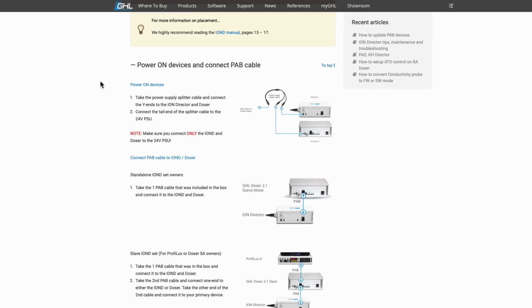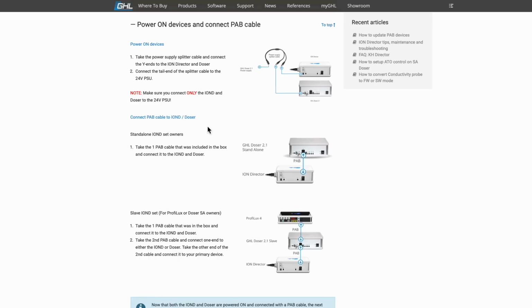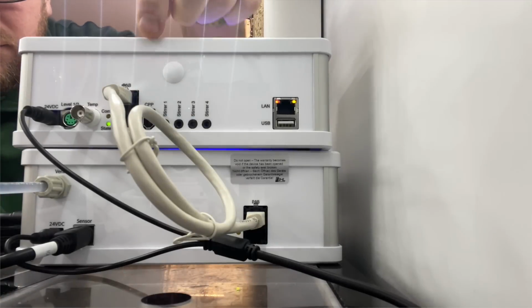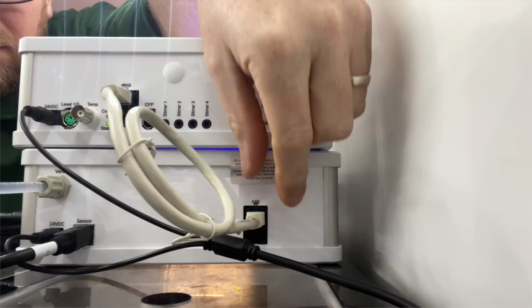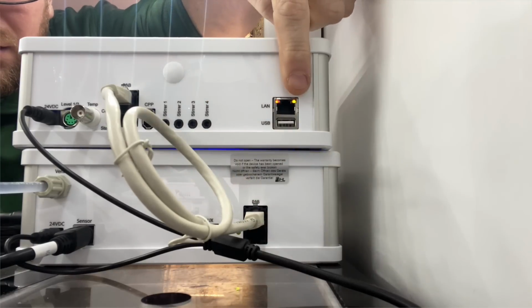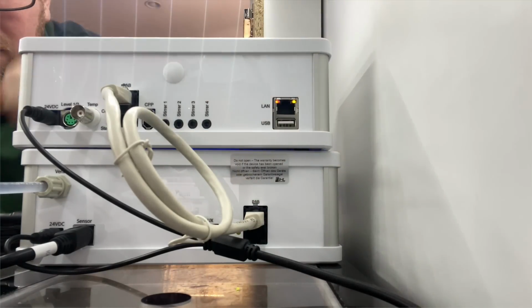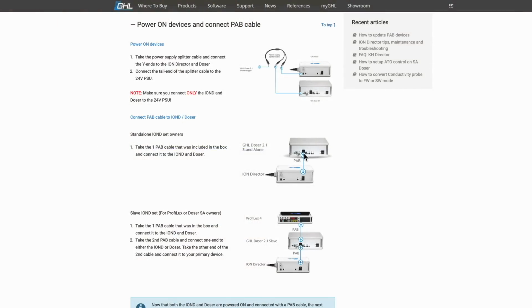The first real step you have to do after just setting it down somewhere is to power it on, which, I don't know, I found interesting. So you find a location, plug the power into both units and turn it on. Easy enough. And you can then connect the PAB cable, which seems odd. I thought you would connect the PAB cable first, but you power it on, then connect the PAB cable, which, like I touched on, is basically that Ethernet cable, but it is labeled PAB on the doser. Don't connect it to the LAN connector. Connect it up to one of the PAB cables and connect it to your Ion Director.